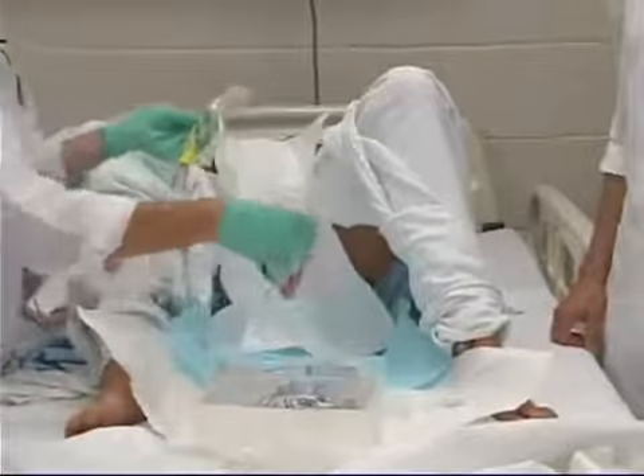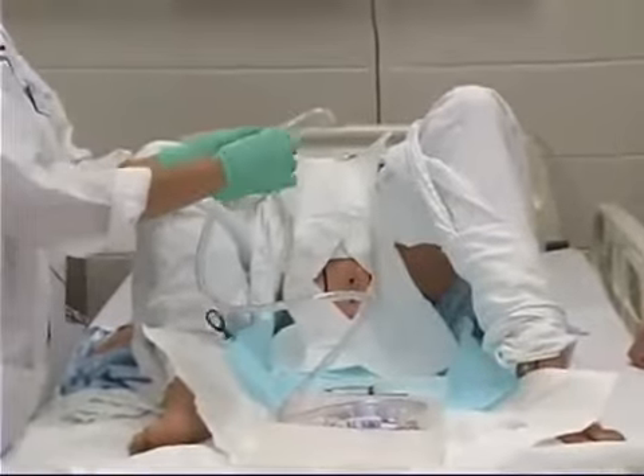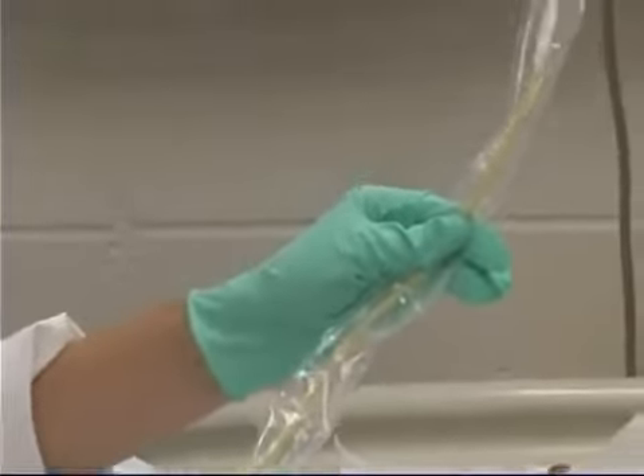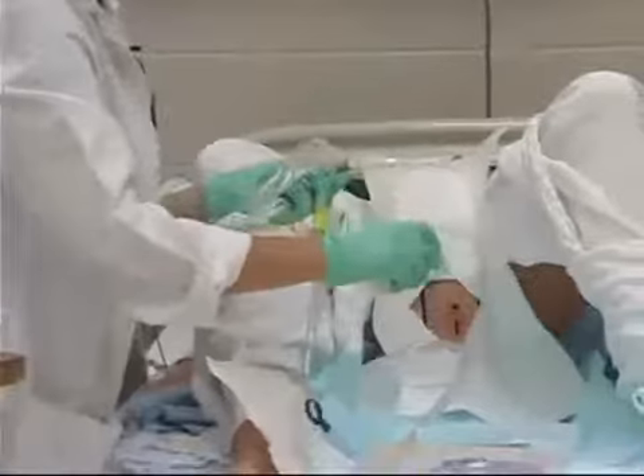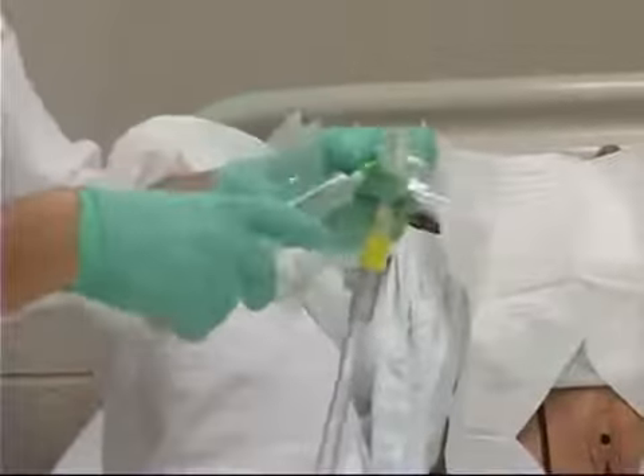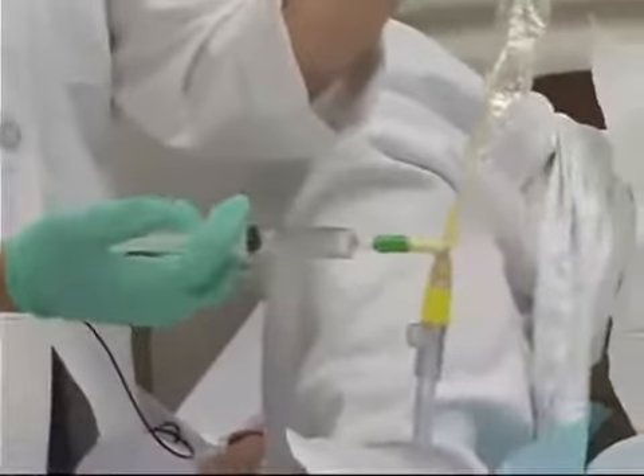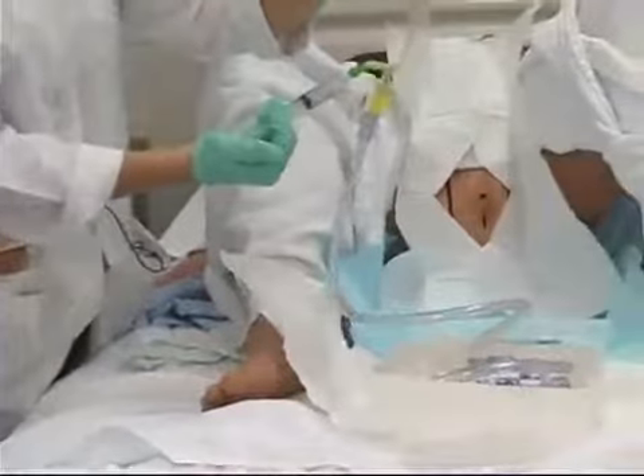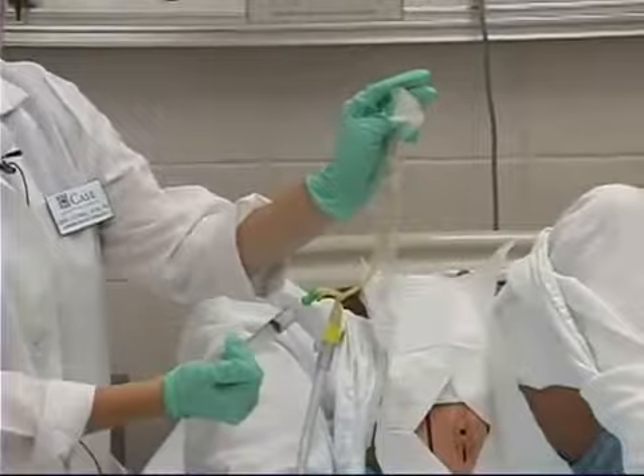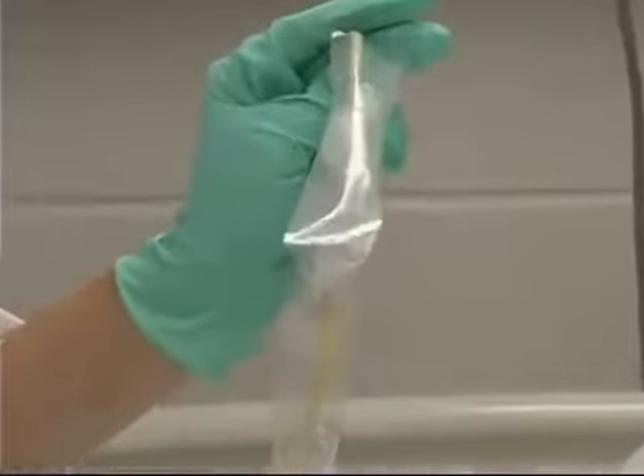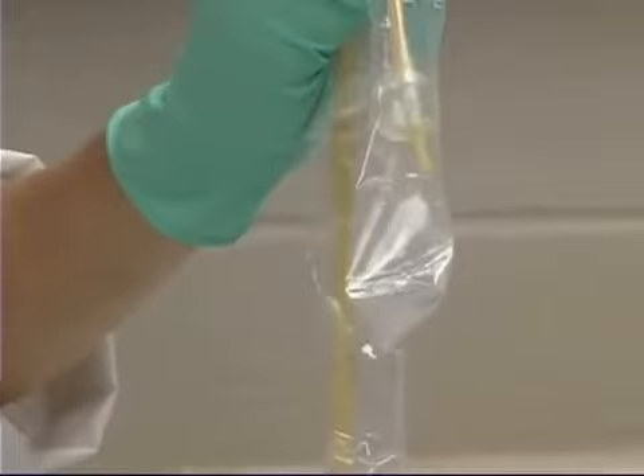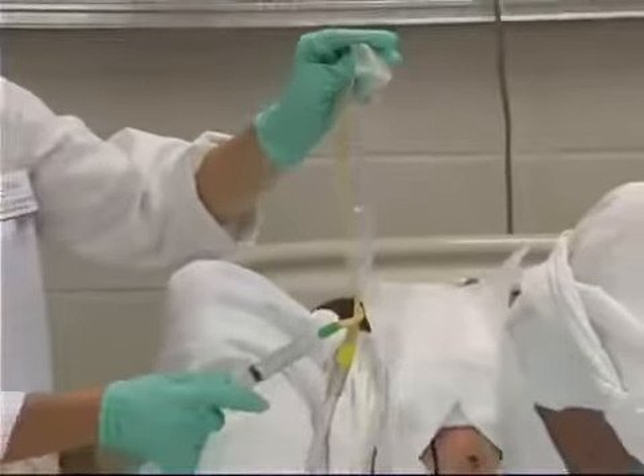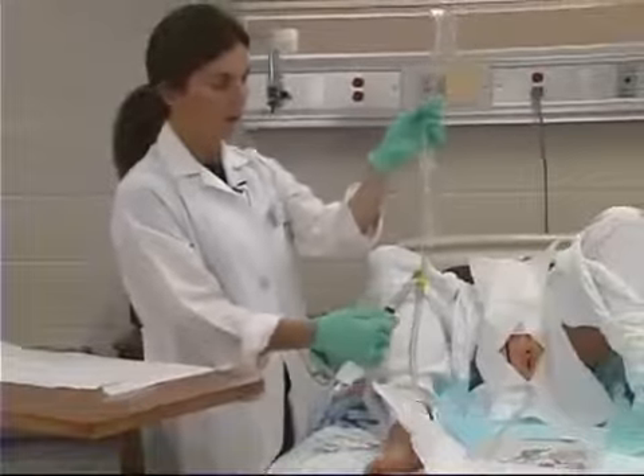What you're going to want to do before you insert this catheter is check your balloon. This valve here is for inflating the balloon, and the catheter is sterile until you remove this sterile sleeve. You take the syringe filled with sterile water, you remove the black cap, and you inflate the balloon. The balloon can hold 10 cc's. You want to inflate it to make sure the balloon inflates. Once you get your balloon inflated and there are no leaks, you deflate the balloon. And you keep your syringe attached for when you're going to insert the catheter.